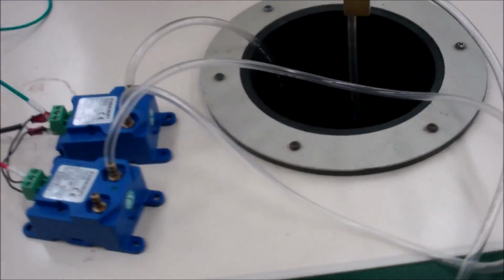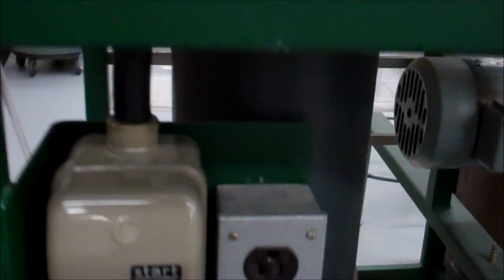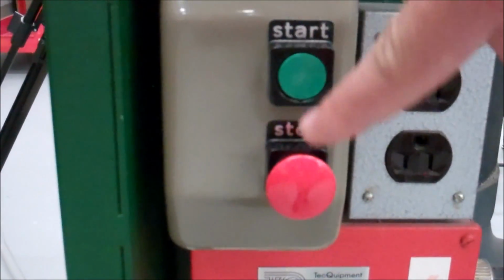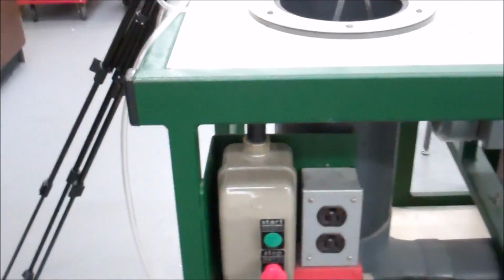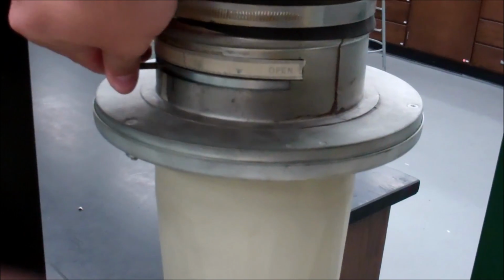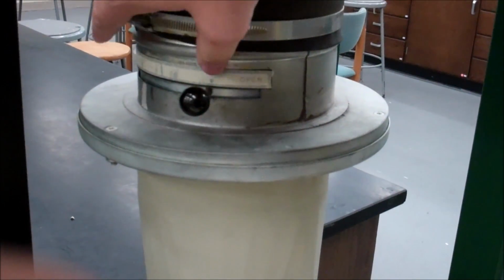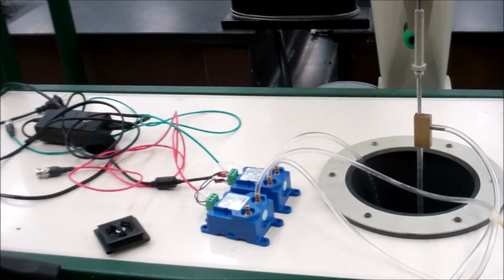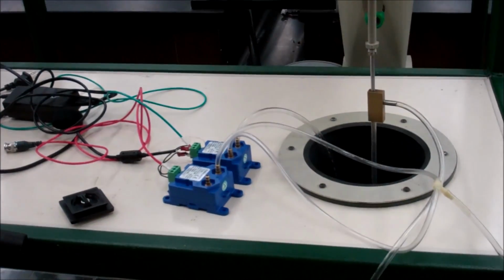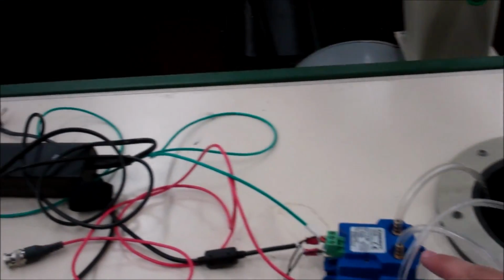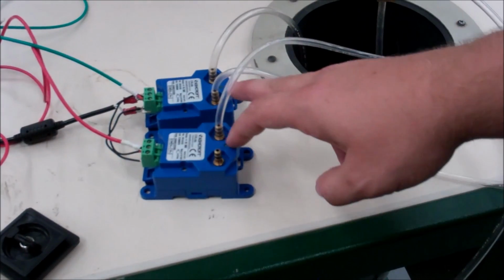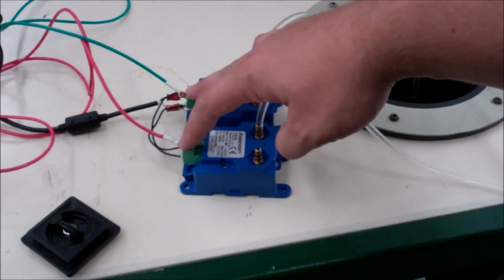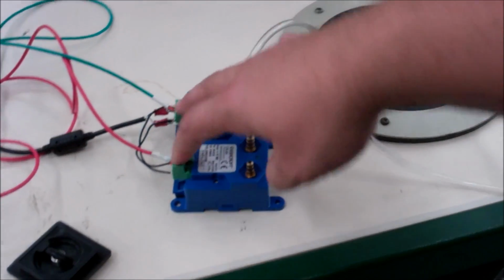And again, to start the flow bench, you come to the side here, you hit the start button. To stop it, you hit stop. And to control the flow rate, again, you have it here. And again, remember, less than 3/4 of the full power. Now, common problems are when the pressure transducer's lights don't come up, make sure the connections are made correctly. So when the light of the pressure transducers don't turn on, make sure that all the connections are made properly.